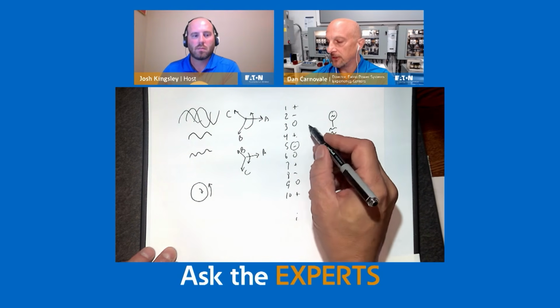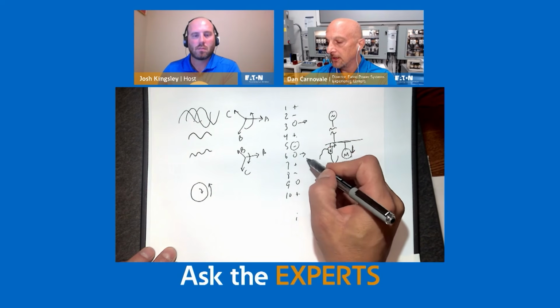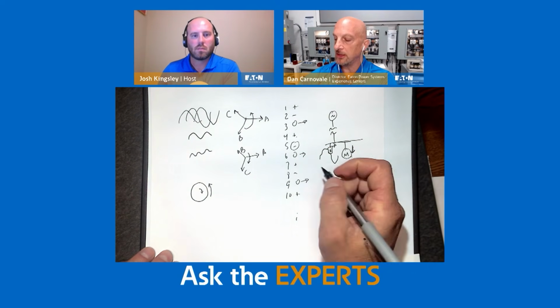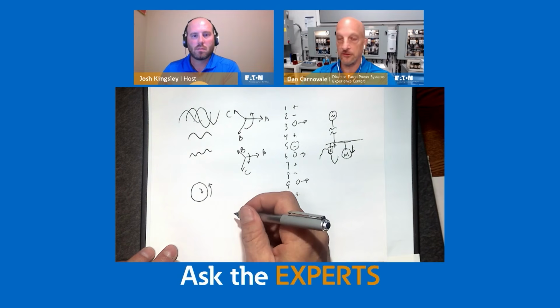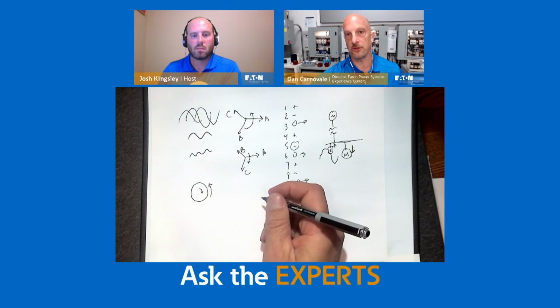Zero sequence harmonics we kind of addressed earlier, and they add up in the neutrals. And so now you can have overheating in the neutrals, to the point where you can have double the current in the neutral as you do on the phases.